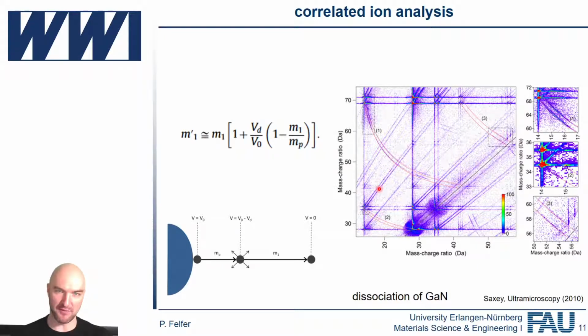But this has become a very important tool, especially in atom probe samples where correlated field evaporation happens a lot, to recover some of the ions. Not quite sure if you recover everything, but you can recover some of the ions. And this is especially prevalent in compound semiconductors, in oxides, in anything with covalent bonding. So a lot of the modern laser atom probe that we do, we're confronted with that a lot.